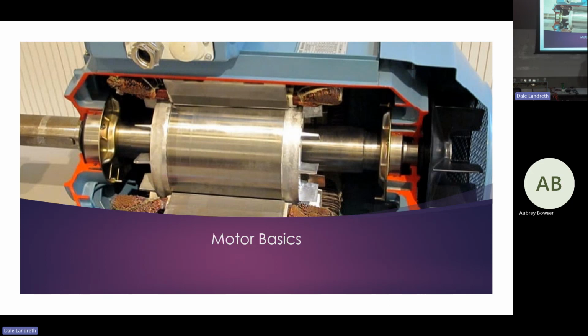On a 6-lead motor, you're going to test it 21 times: going from terminal 1 to ground, 2 to ground, 3 to ground, testing them all to ground, and then testing each winding to each other—1 to 2, 1 to 3, 1 to 4, 1 to 5, 1 to 6, 2 to 3, 2 to 4, 2 to 5, 2 to 6, and so on until they're all tested. You'll actually test the motor twice, because when testing lead to lead, you test 1 to 3, then turn around and test 3 to the other winding. So you basically start with 1 and work your way down the line.